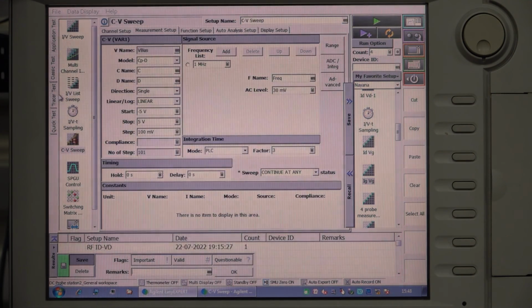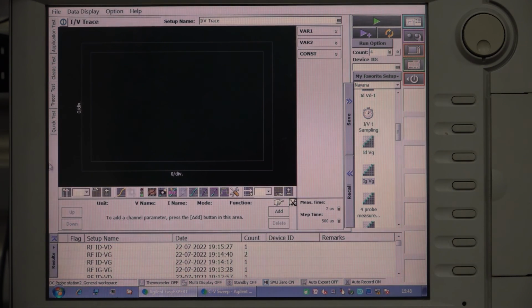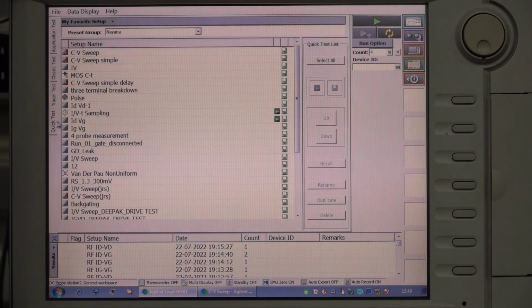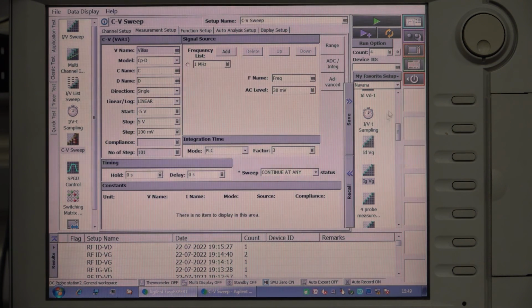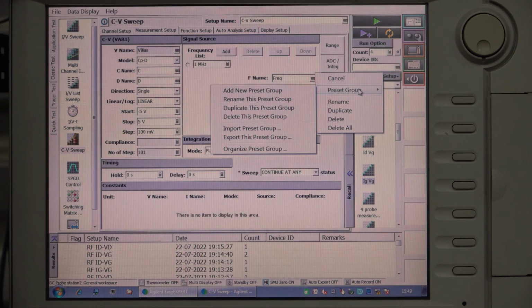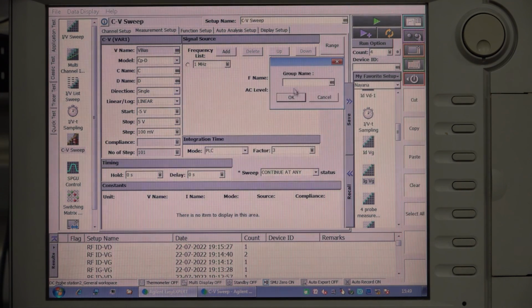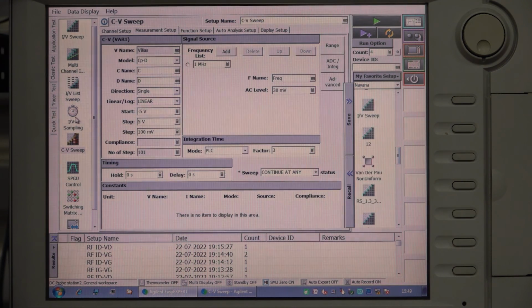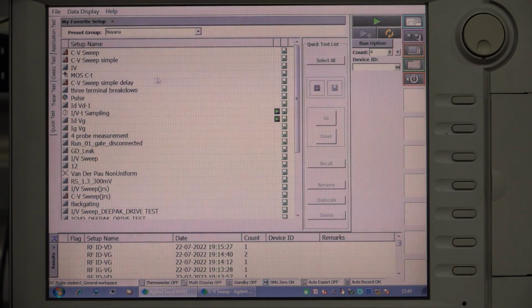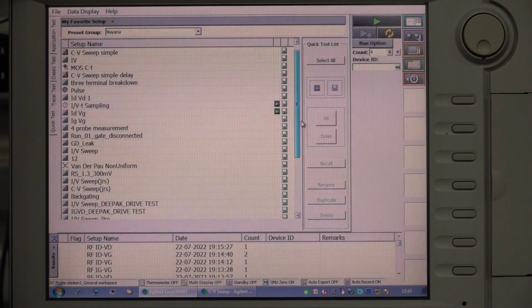Now when we go to this tracer test, it basically acts like an oscilloscope, so you can generate traces here like an oscilloscope graph. With quick test, we can generate measurement test setups here. If you go to favorite setup, preset group, add preset group, you can add a name here and generate the measurement setup by saving the name. With quick test, you can get all the measurements here, and if you select a particular measurement and press the green run button, that measurement will run.